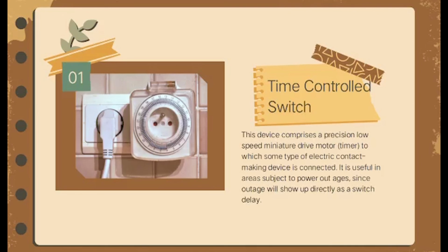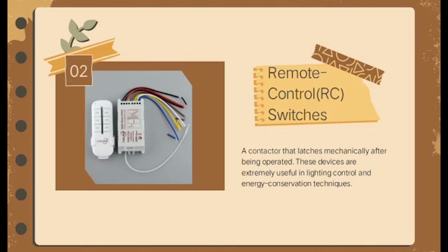Time-controlled switch. This device comprises a precision low-speed miniature drive motor, or the timer, to which some type of electric contact making device is connected. It is useful in areas subject to power outages, since an outage will show up directly as a switch delay. Remote control switches: a contactor that latches mechanically after being operated. These devices are extremely useful in lighting control and energy conservation techniques.